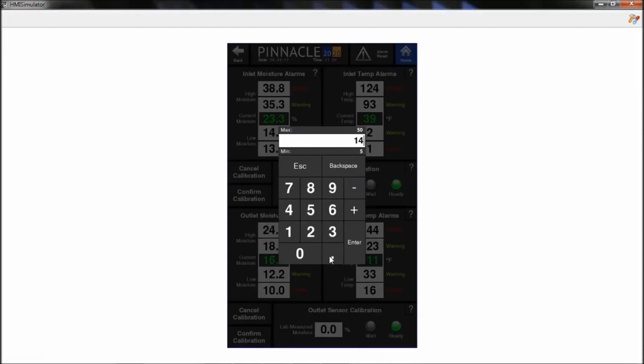Just a note that the maximum this can change on one calibration is 0.5%. If your sensor is reading off by several percent, you're going to have to do several calibrations. The reason we've done that is, one, to avoid an issue where somebody accidentally forgets to put in a digit and all of a sudden they're off by 10% or something like that.